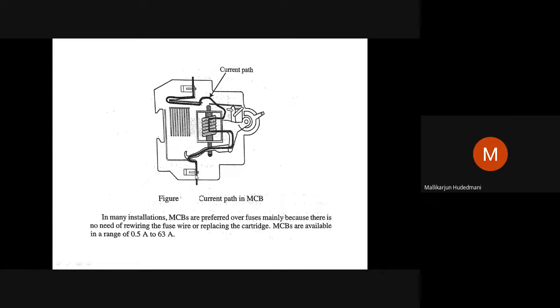This screw which is going out, the terminal giving an external connection, has a J-shaped arm. You can see this J-shaped moving arm. This arm is establishing a contact with the metal wire, which is keeping a contact here. If this J-like structure lifts up, it means the electrical contact is opened up here. That's called the circuit is broken. In that way, this lifting mechanism works: the bimetallic strip, due to the flow of current through it, when it heats up, will automatically deform in its shape. It is arranged in such a way that the overcurrent flowing on that metal strip will lift its contact, and automatically the lifting of this contact means this mechanism is such that the lever trips off, falls down. Falls down means the electrical circuit is broken.